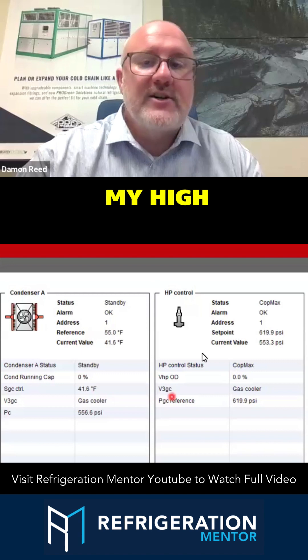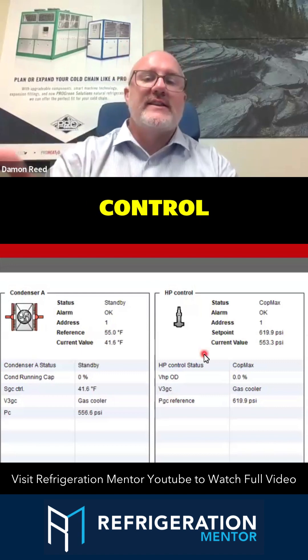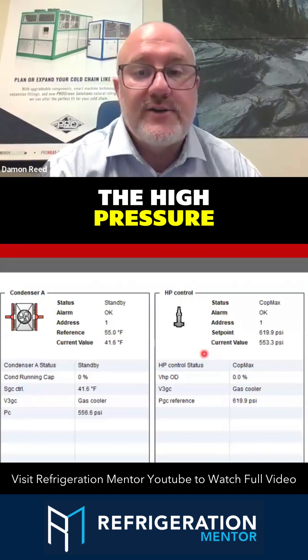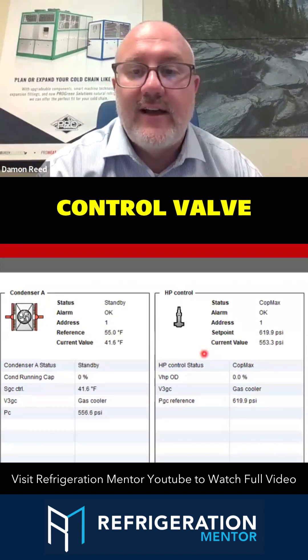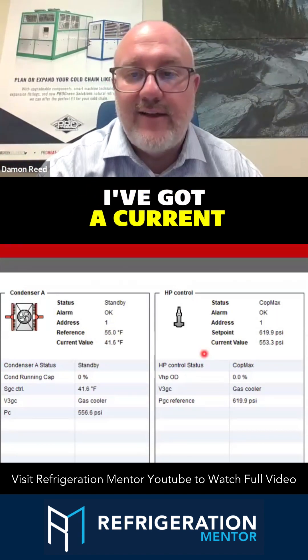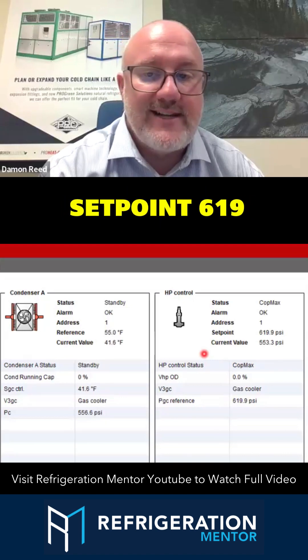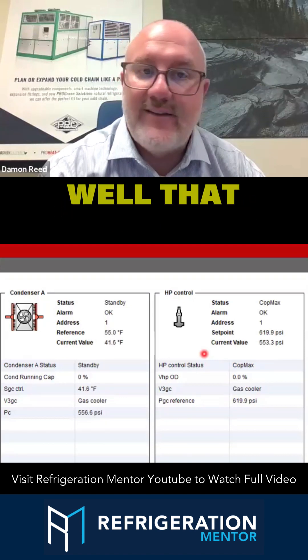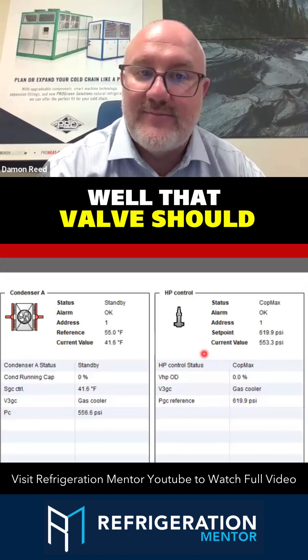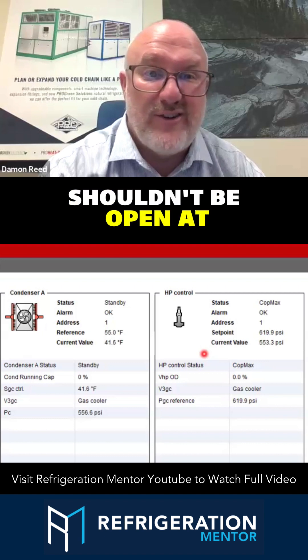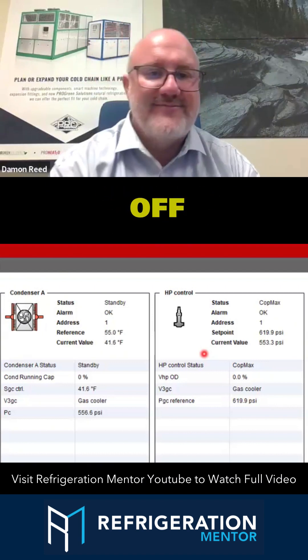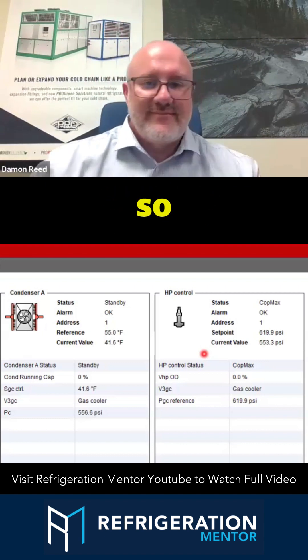Jumping over to my high pressure control — this is where I'm controlling the high pressure control valve. I've got a current value of 550 and a set point of 619. That valve shouldn't be open at all right now, and it's not — it's off. So that's expected.